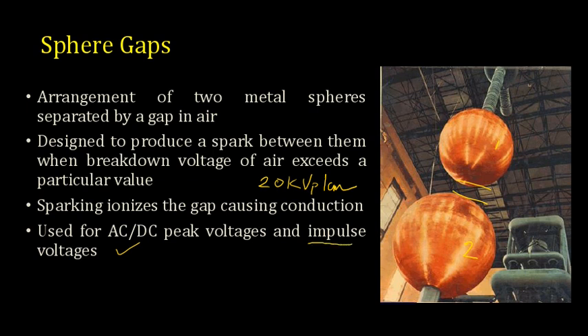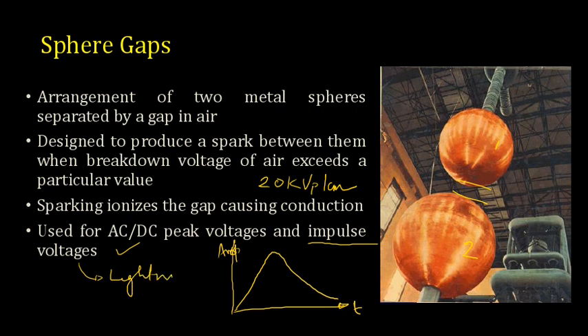Now impulse voltage is very similar to lightning voltage, or the voltage waveform of lightning. So you'll have a waveform something like this. This is your time and this is the amplitude. So the impulse voltage will look like this. It will have a steep rise and then a slow fall. Such voltage is known as impulse voltage. You can think of it like lightning. Such voltages can also be measured using this sphere gap.